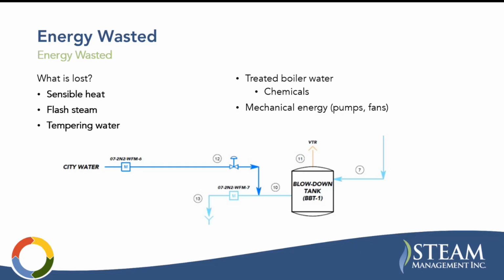What is lost? So you have your sensible heat, obviously just heat in the blowdown that you could capture. When that blowdown drops pressure, some of it flashes, say 10, 13%. That is clean steam. So that flashes as clean steam, just like the steam in the boiler leaves the impurities behind. So does that flash steam. So that could be used if you can capture it.